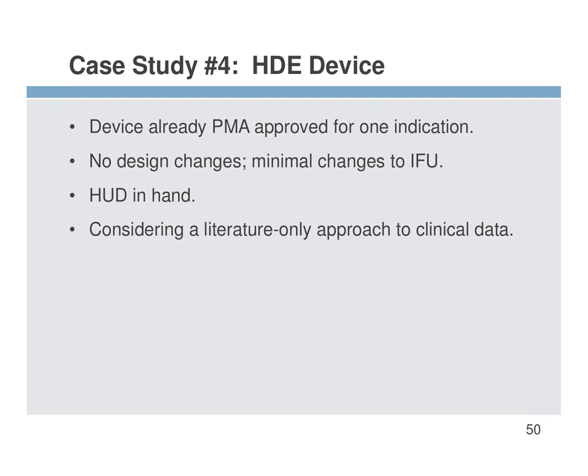And so I called up the branch chief, and the branch chief said, whatever you do, please let's have a pre-HDE meeting, because FDA doesn't really like a 75-day time frame for an HDE. I mean, they get 90 days for a 510K, and presumably HDE is sort of like a PMA, but not having to prove safety. But there's a lot of questions that they're going to ask, and 75 days isn't time to ask them, so they almost always want a pre-HDE meeting. So there's just a little tidbit of information.